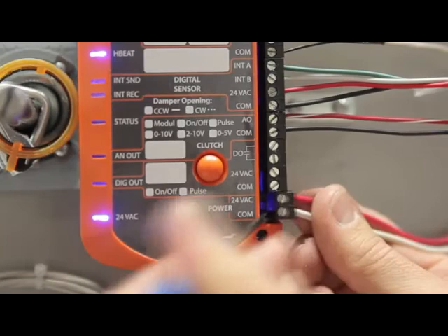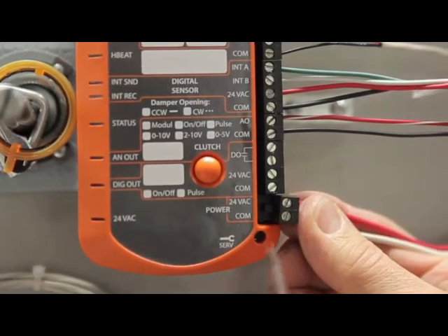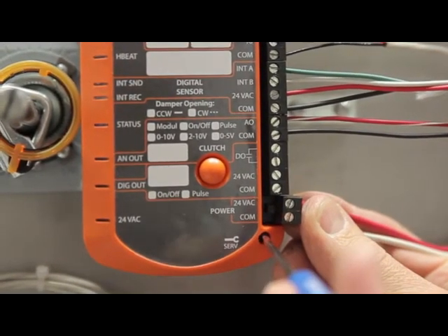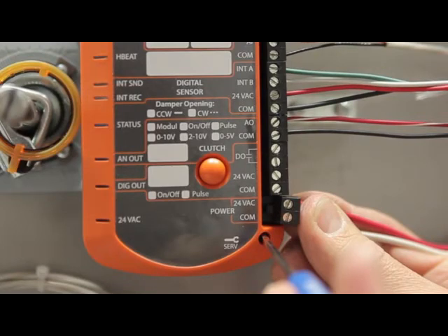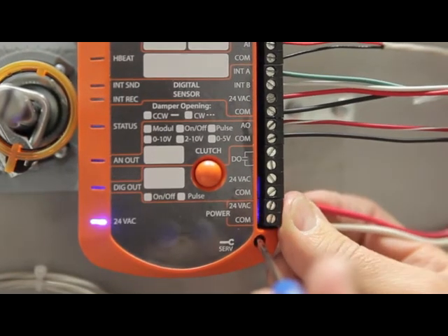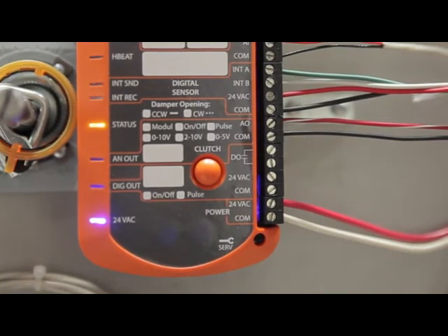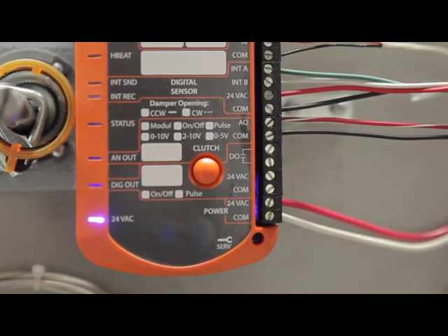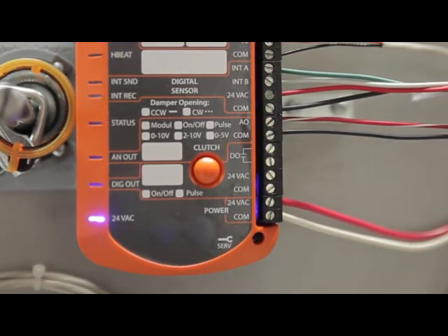First, unpower the controller by pulling out the supply terminal block. Press and hold the service button on the front of the controller using a screwdriver. While pressed, reconnect the supply terminal block, then release the button. Notice the status light's behavior confirming a different sense of rotation.